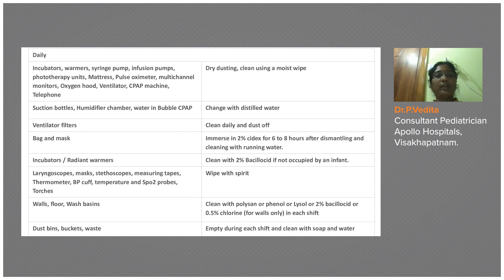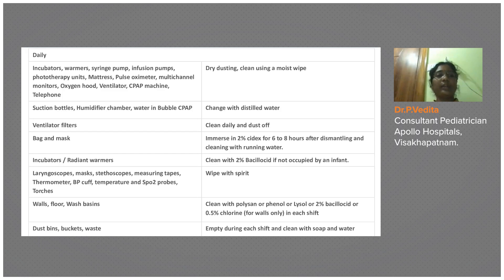Pulse oximeters, suction bottles, and humidifiers — change the distilled water daily. Ventilator filters should be cleaned daily to remove dust. Bag and mask should be cleaned with 2% Cidex for six to eight hours after dismantling. Incubators and radiant warmers, if not occupied by an infant, should be cleaned with this agent; if occupied, just clean the warmer surfaces.